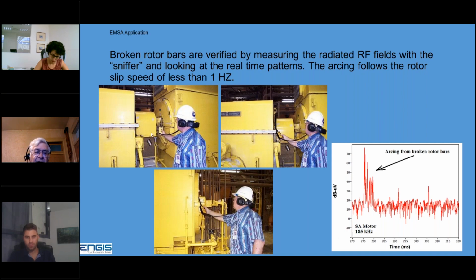And how you verify that was this little device we call an EMI sniffer. We check the outboard bearing, we check the inboard bearing, we check on the other side of the coupling. So if you pick up here and here, and it's this arcing at a very low frequency, that's a broken rotor bar.